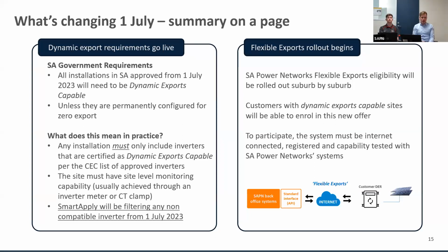So what does this mean in practice? Any installation must only include inverters classified as dynamic exports capable per the CEC approved list that Ian's already mentioned, which we'll talk about later. The site must also have site-level monitoring capability, usually achieved through an inverter meter or a CT clamp on site.